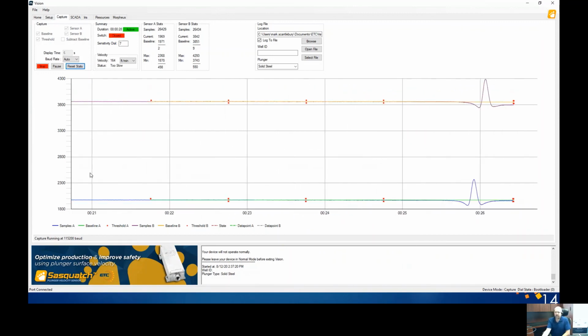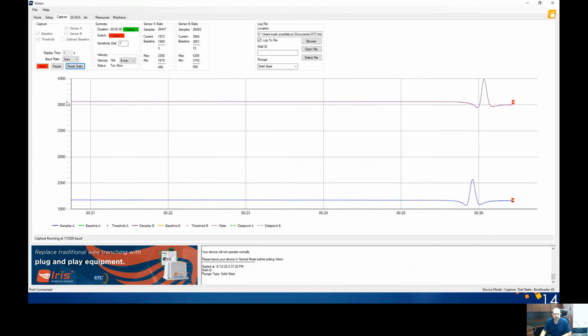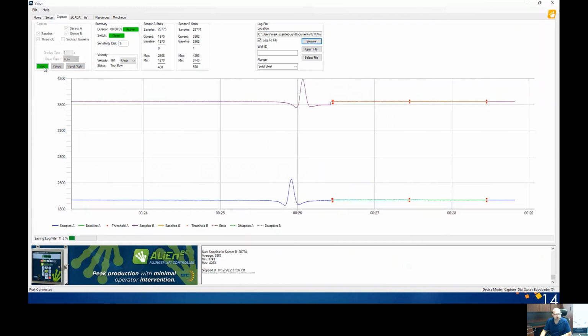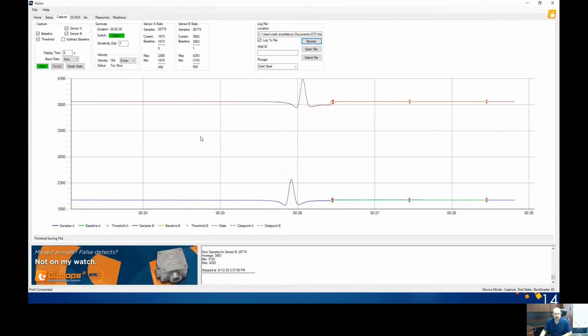And you can see that when I do that, I'm just going to stop it here so that we can see what's happening. It will start automatically looking again once that reinitialize timer goes. But if we stop here and look at what's happened, you can see the same waveform here. We see it dip and then go up, and you can see that there's that time difference. And then eventually it goes back to monitoring again. But if you're messing with the sensitivity dial switch before you do your capture, it might not start recording data right away because it's paused while it collects data and analyzes the velocity. It will start to spit out data pretty quickly. So that's just a quick example.